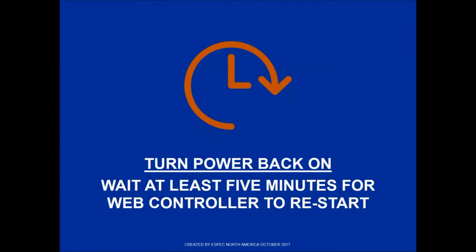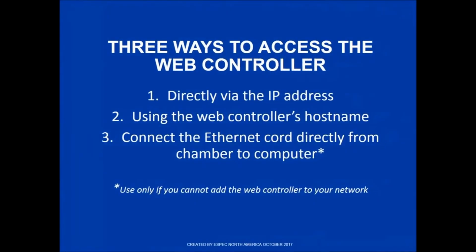Now you're ready to access the web controller on your computer. There are three different ways to do this: directly via the IP address, using the web controller's host name, or connecting the Ethernet cord directly from the chamber to the computer.